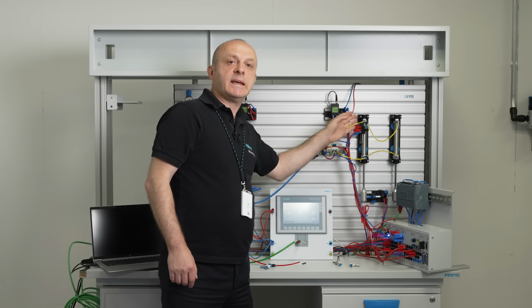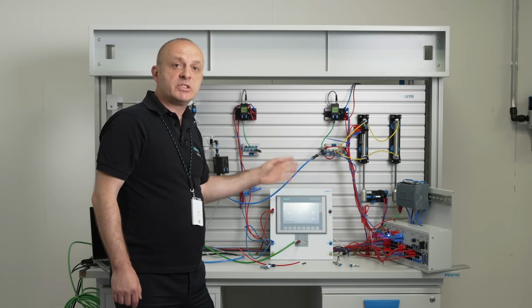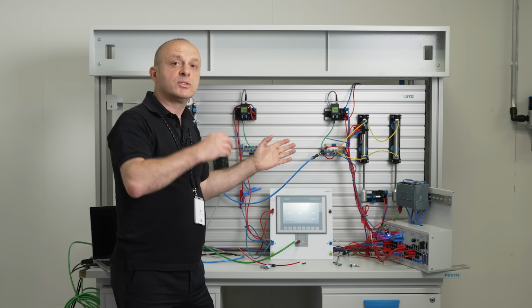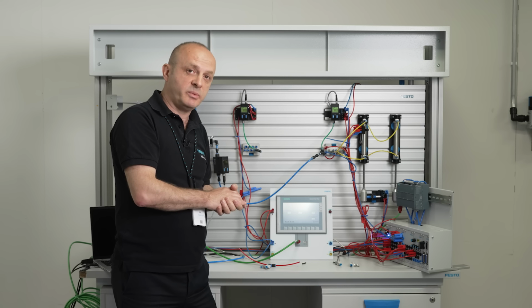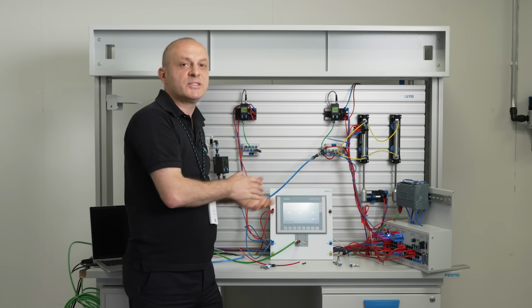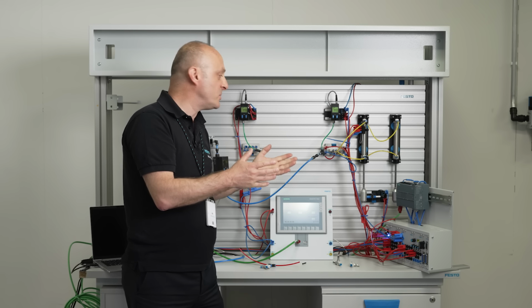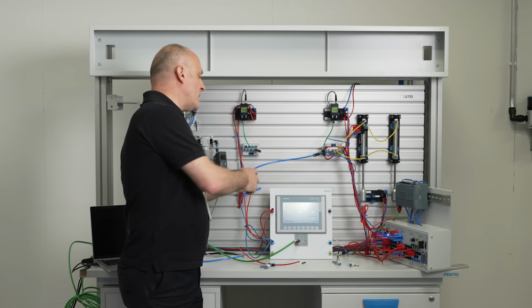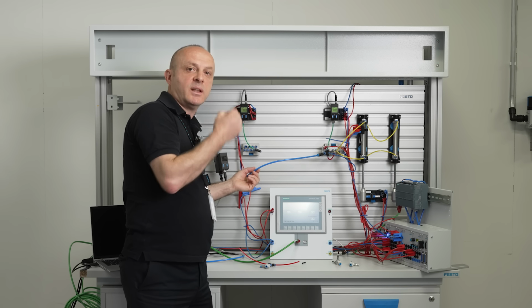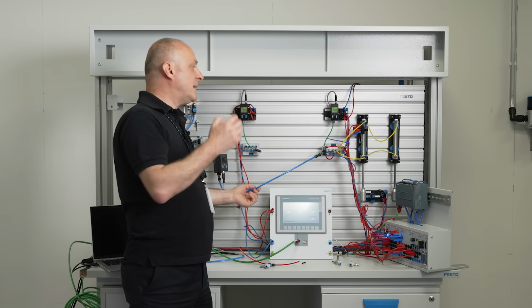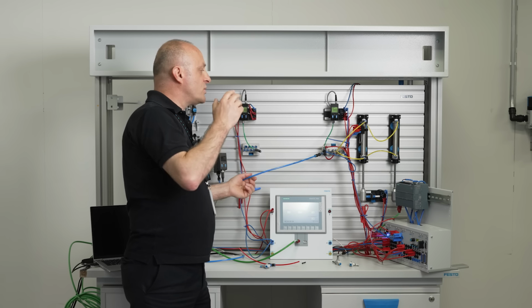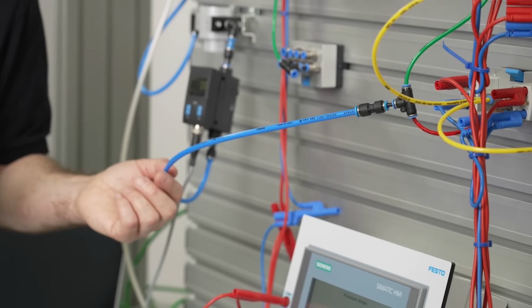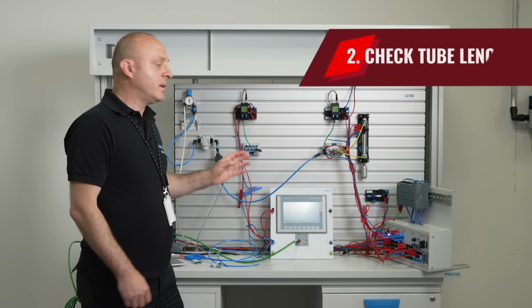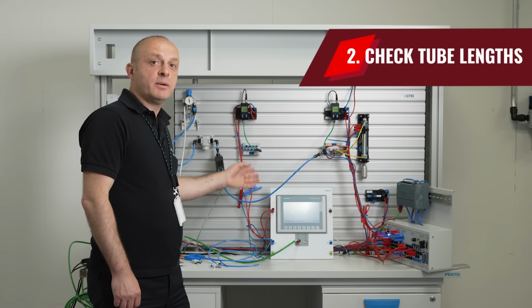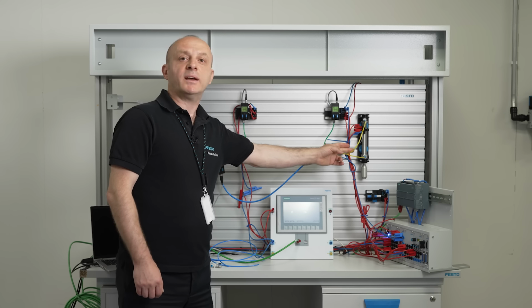Earlier on, when we added the second cylinder, the machine stopped and we had a fault. So there was nothing wrong with the machine. You can replace any parts you like on the machine, but there is nothing wrong with it, because the problem was our tube diameter wasn't large enough. So when we deal with troubleshooting, we need to make sure we can provide enough pneumatic power. Last time we had a look at the pressure drops and the leakages, but this time we have a look at the tube length and its effects.